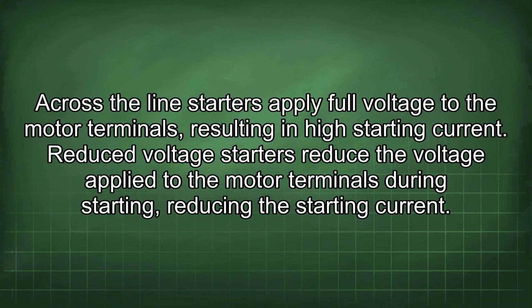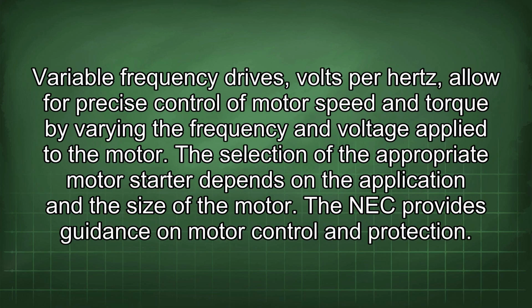Across-the-line starters apply full voltage to the motor terminals, resulting in high starting current. Reduced-voltage starters reduce the voltage applied to the motor terminals during starting, reducing the starting current. Variable frequency drives, volts per hertz, allow for precise control of motor speed and torque by varying the frequency and voltage applied to the motor. The selection of the appropriate motor starter depends on the application and the size of the motor. The NEC provides guidance on motor control and protection.